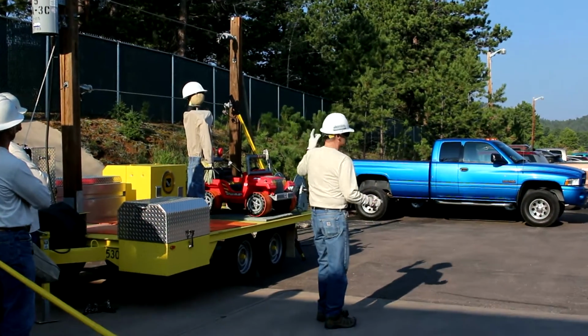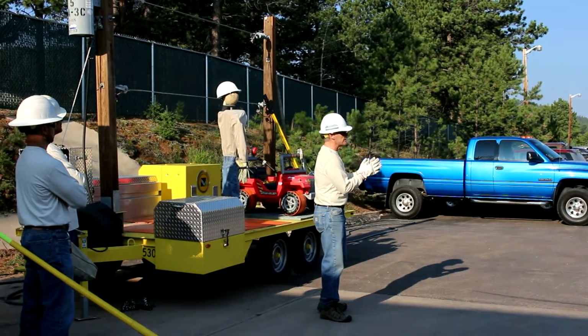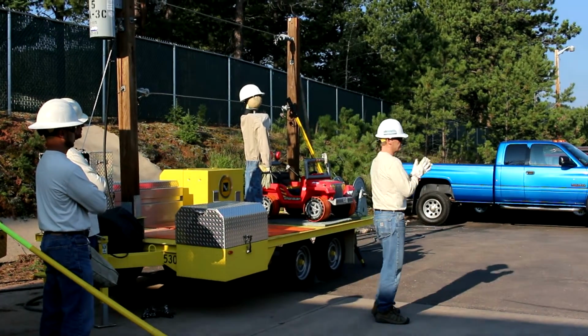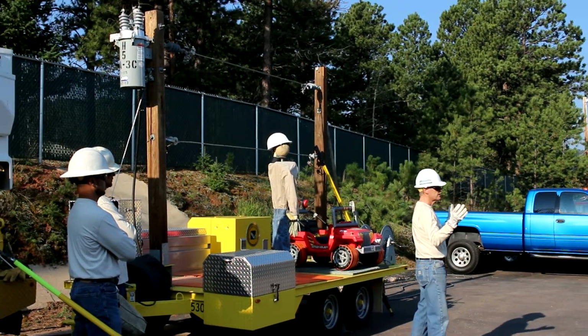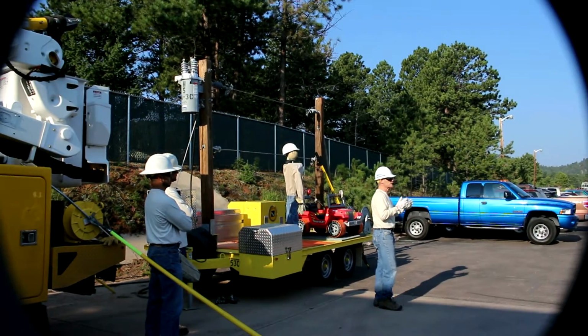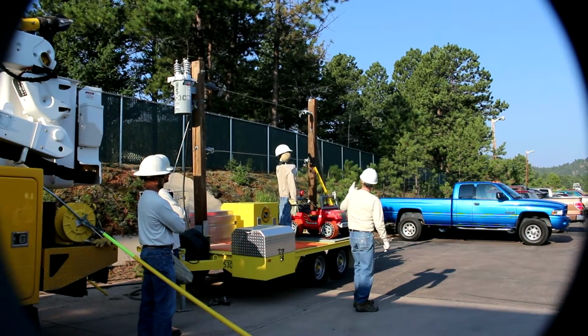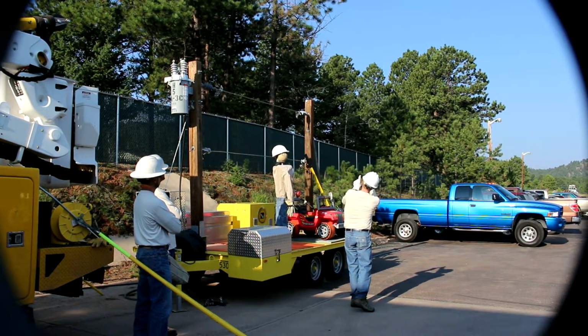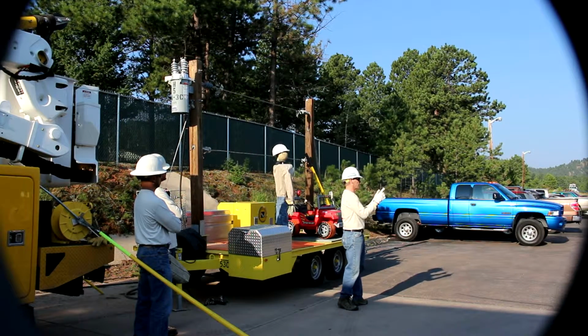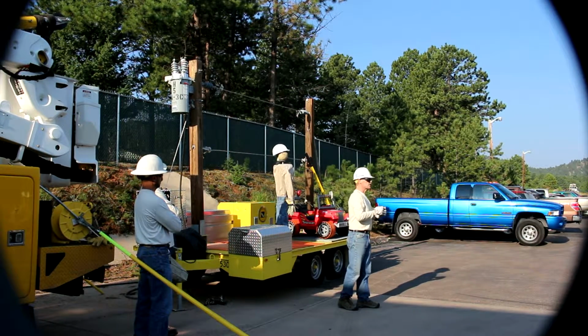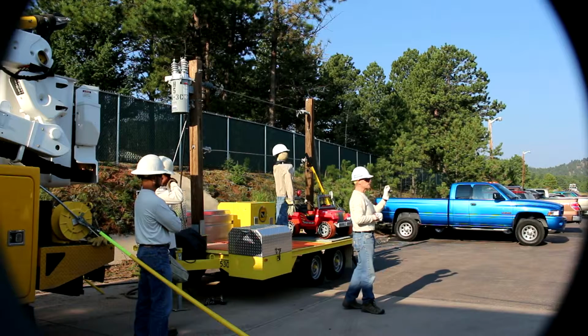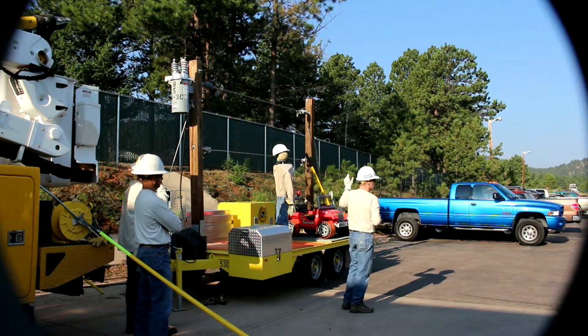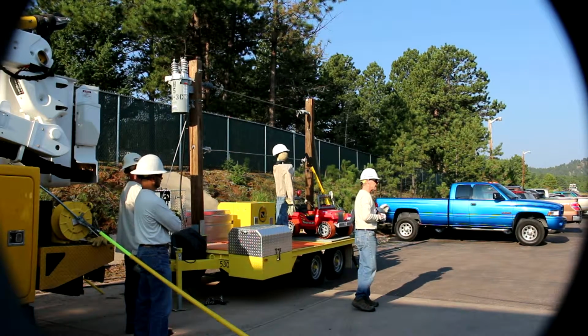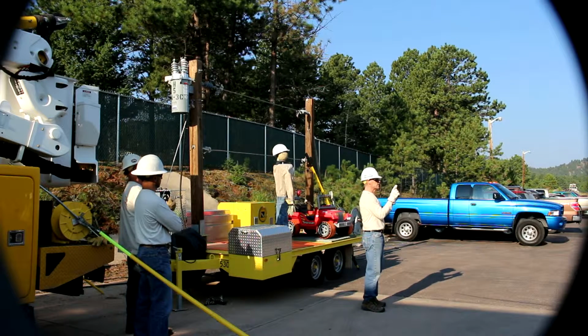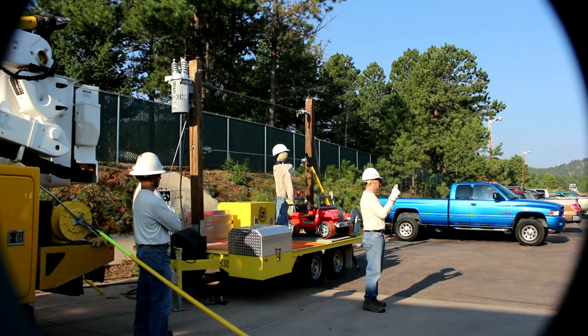You'll notice everybody says that if there's an accident, they say that it jumped out and got them - electricity jumped. Well, we're going to show you electricity doesn't jump. Matter of fact, right here, that little plastic bell is 9 inches long, and according to the standards in the industry, you only need 1 inch per 1,000 volts. So we have 7,200 volts we're going to energize that at. It doesn't jump 9 inches.